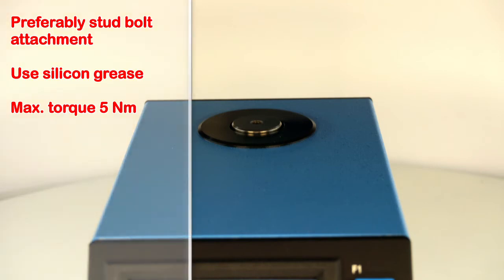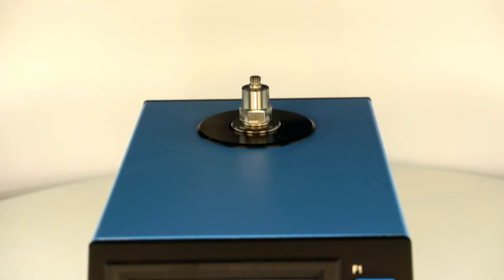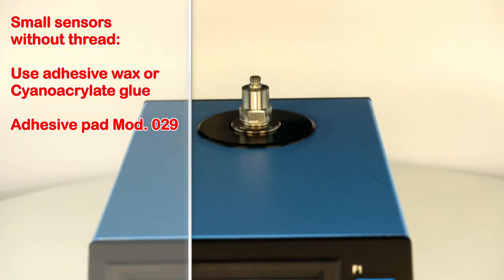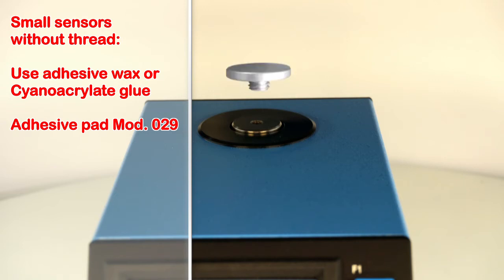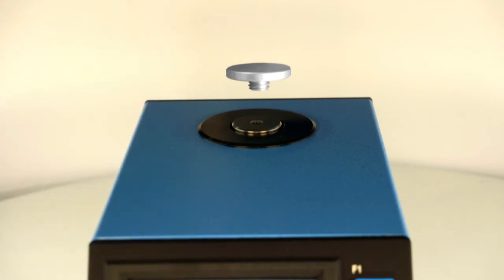First, screw the sensor onto the vibration shaker using a stud bolt or thread adapter. The coupling surface of the sensor should be lubricated with silicone grease to improve transmission. The sensor needs to be screwed on tightly, however the torque should not exceed 5 Newton meters. Small sensors often don't have a mounting thread. In this case you can use adhesive wax or cyanoacrylate. Alternatively, to safeguard the shaker head, use a Metra Type 29 adhesive pad.